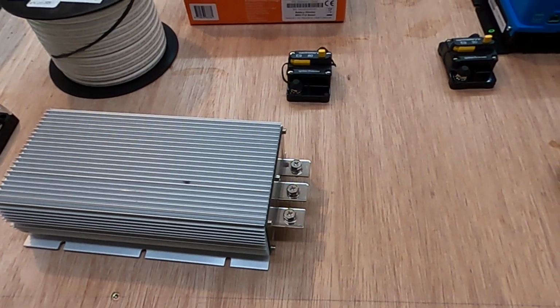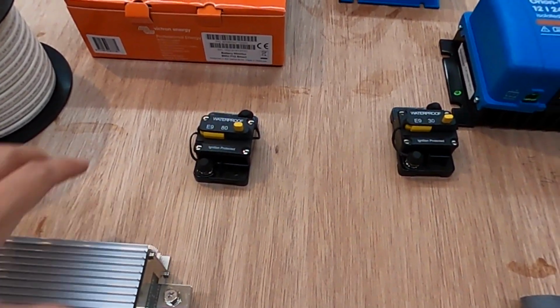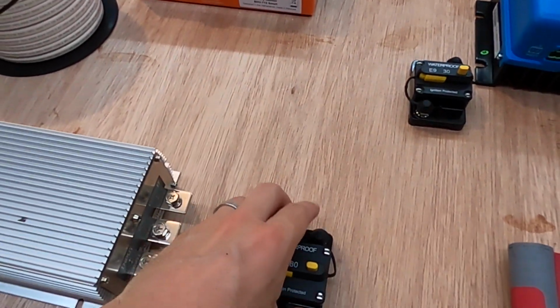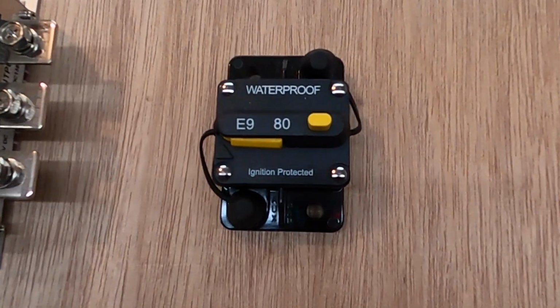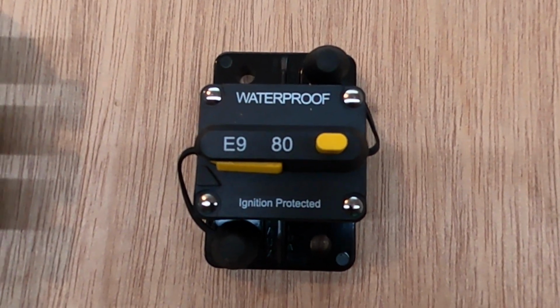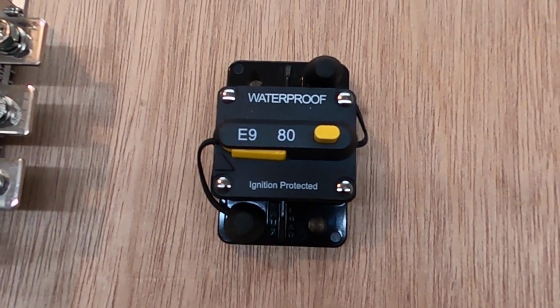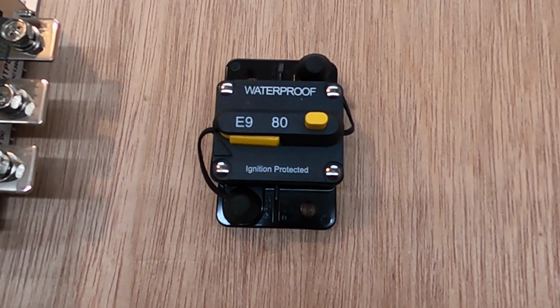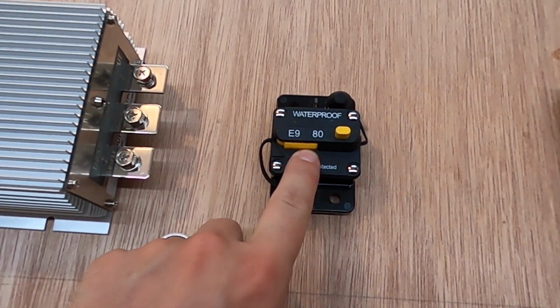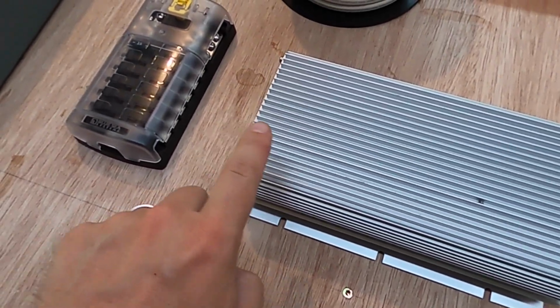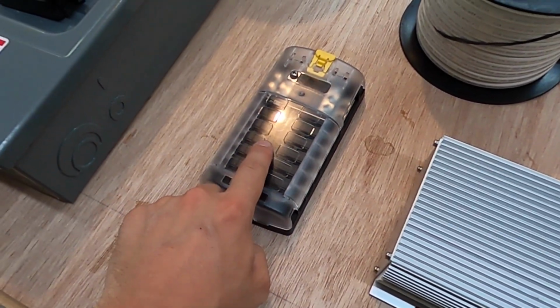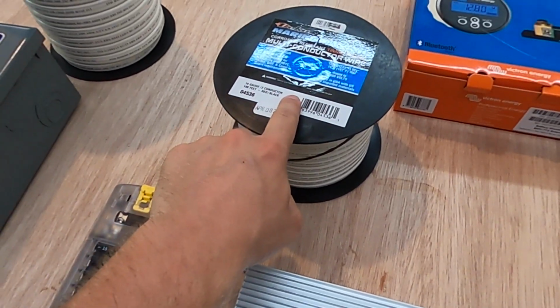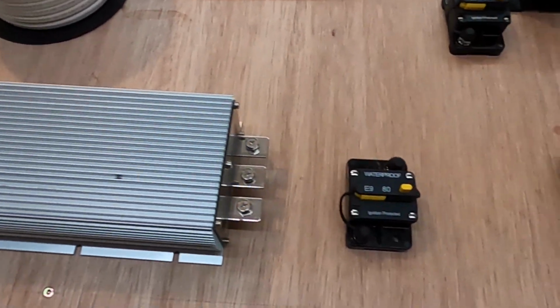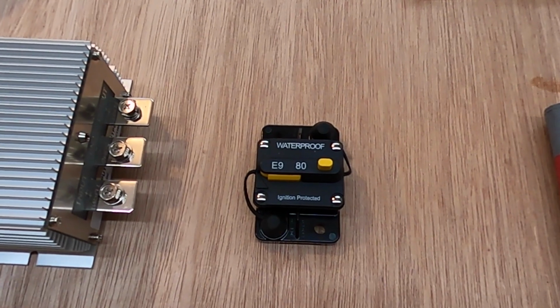Going back through the system a little bit, on the other side of our step-down inverter we've got our thermal fuse here, or actually it's a thermal circuit breaker. This circuit breaker will protect everything downstream through the step-down inverter, through our fuse block, and through our wiring to all of our main components. This is an 80 amp resettable circuit breaker.